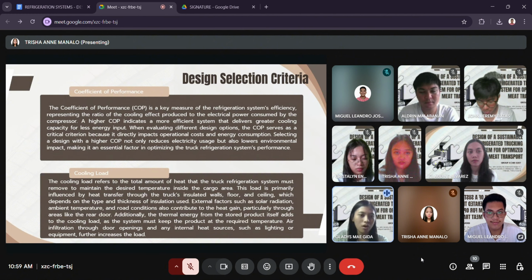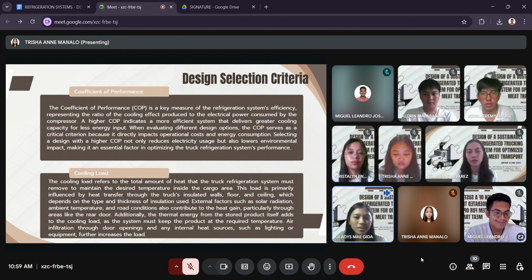Third is the coefficient of performance. It is a key measure of the refrigeration system's efficiency, representing the ratio of the cooling effect produced to the electrical power consumed by the compressor. A higher COP indicates a more efficient system that delivers greater cooling capacity for less energy input. When evaluating different design options, the COP serves as a critical criterion because it directly impacts operational costs and energy consumption. Selecting a design with a higher COP not only reduces electricity usage but also lowers environmental impact, making it an essential factor in optimizing the truck refrigeration system's performance.